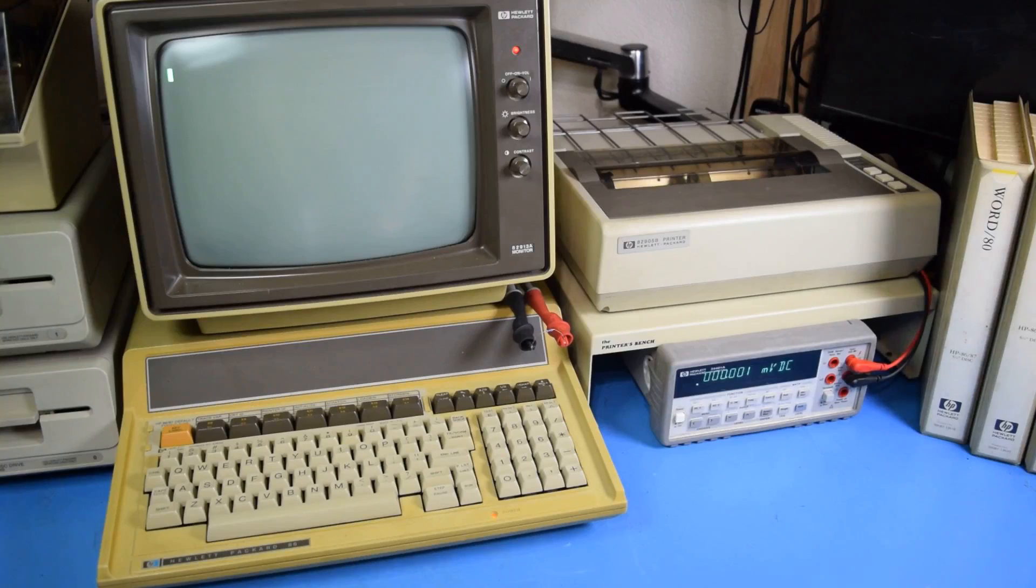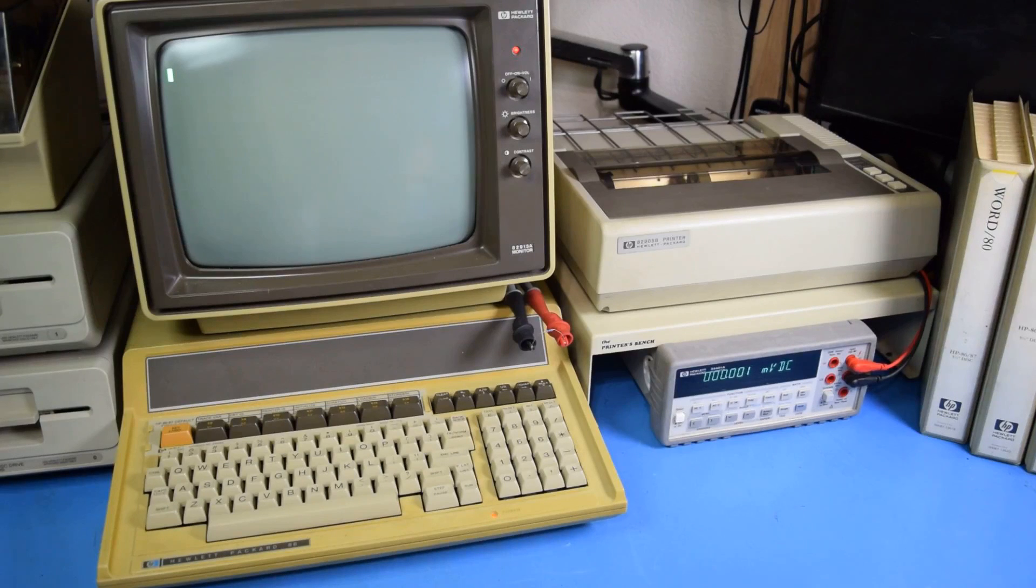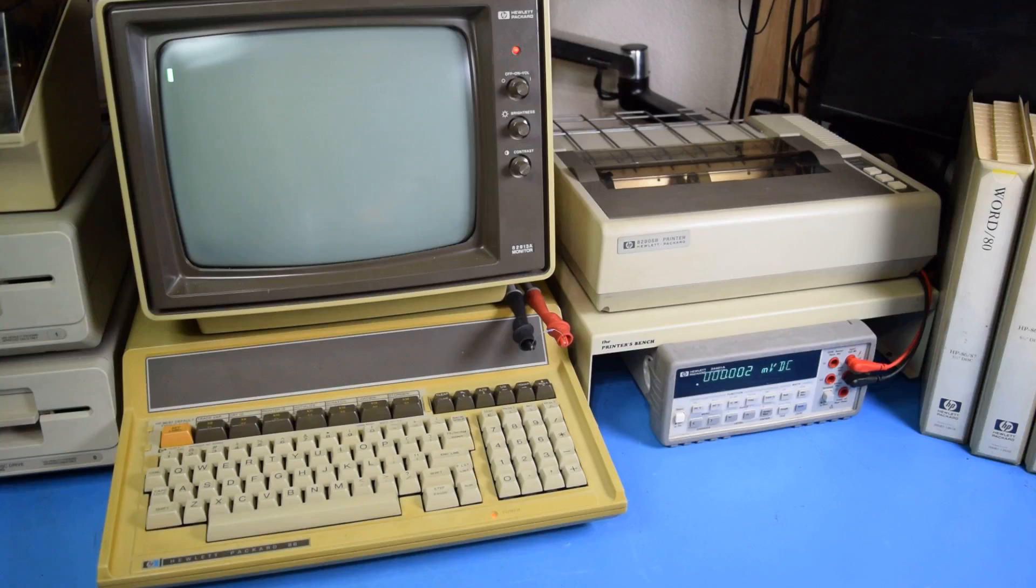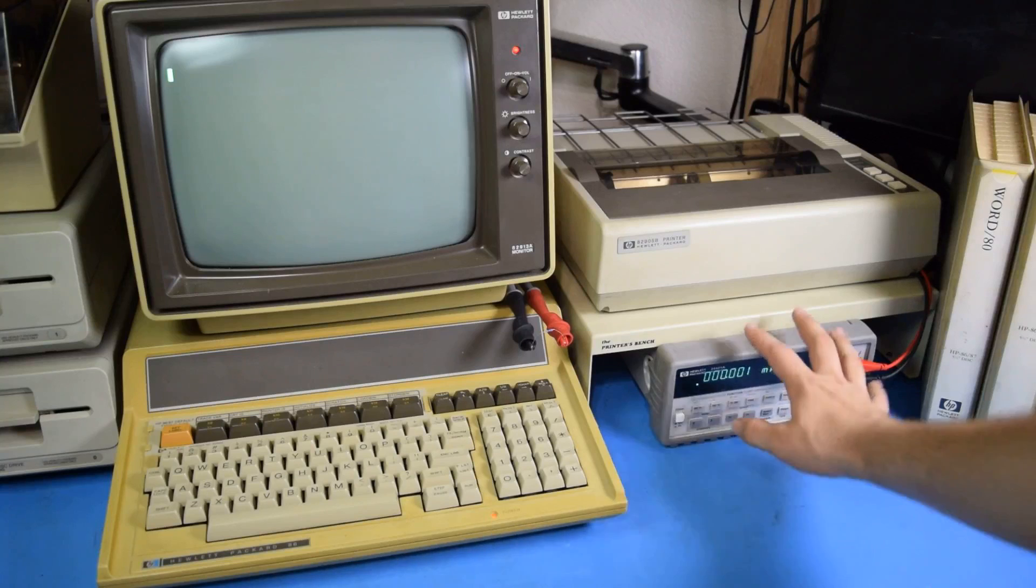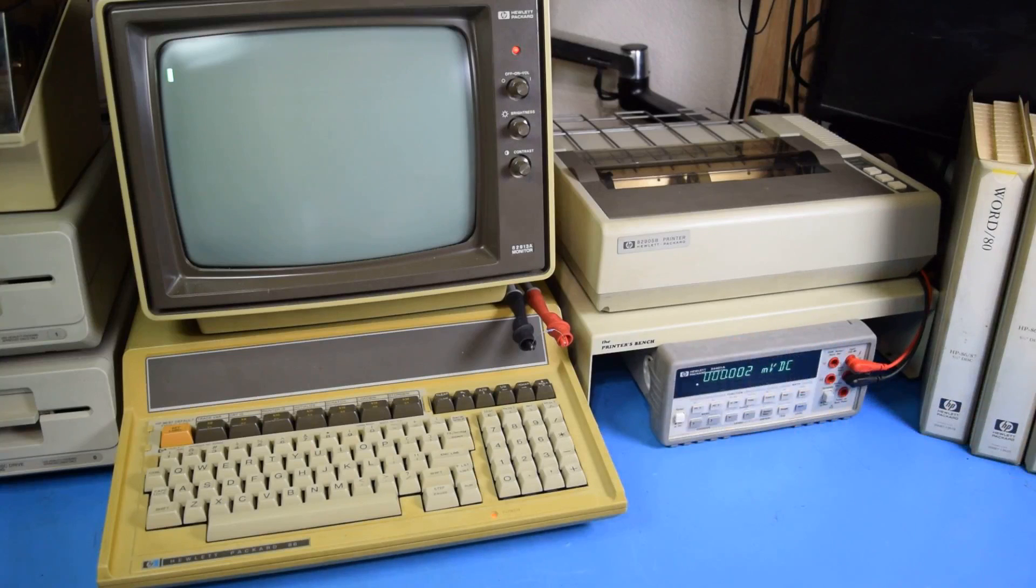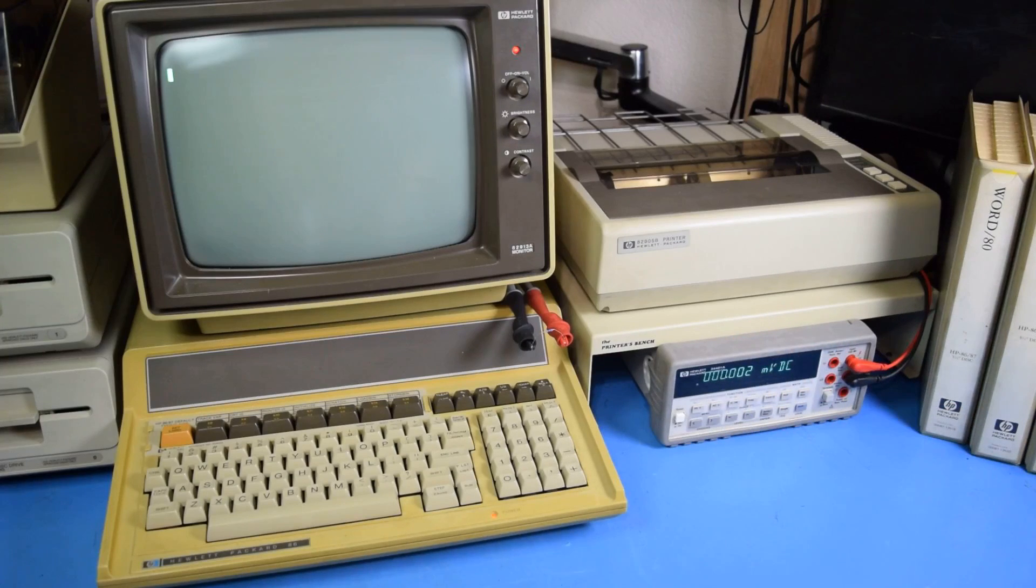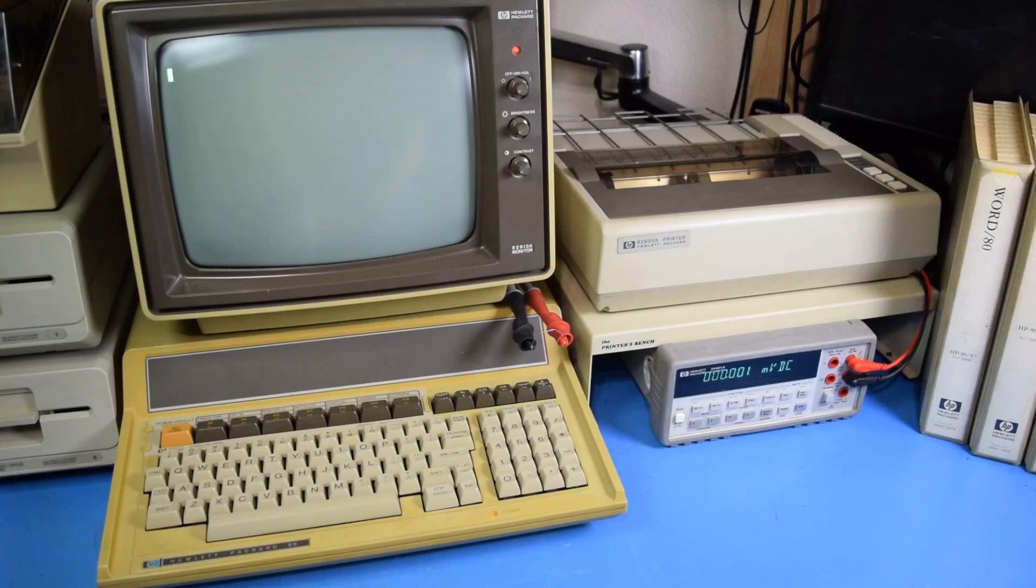Now to use this multimeter with the computer, we have to make sure that it's set to GPIB mode because it can only be used with RS-232 or GPIB independently, and we have to make sure we know what the GPIB address is that we can change in the menus. Once that's done, we can start communicating with it from the computer.